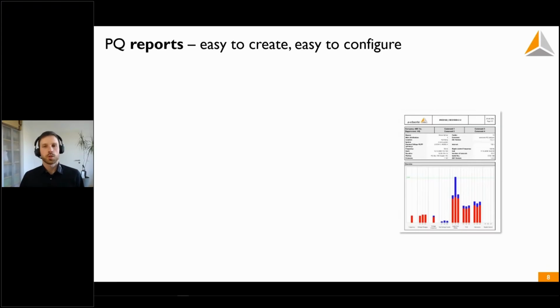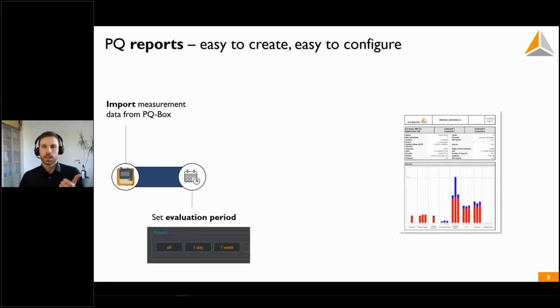So after you finished your recording, you can import the measurement data from the PQ-Box. When the measurement data is on your PC, you can open the measurement file. PQ-Mobil automatically asks you what period you want to open. If you have a measurement for over 2, 3, or 4 weeks, for example, you can select whether you want to open all measurement data. That's what I usually recommend, to see everything that was going on, or you can limit the period to a day, a week, or a month if you want. You can change this afterwards in PQ-Mobil as well.